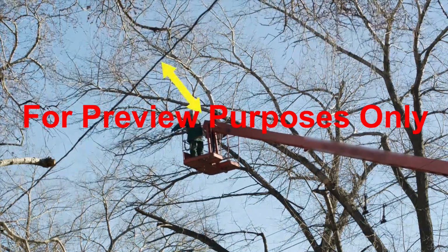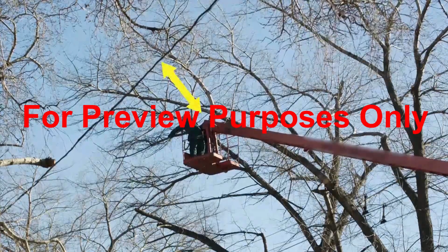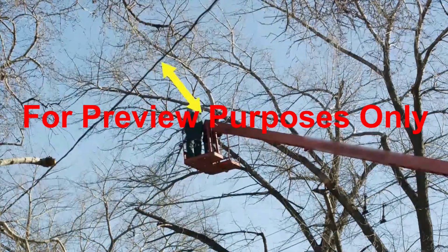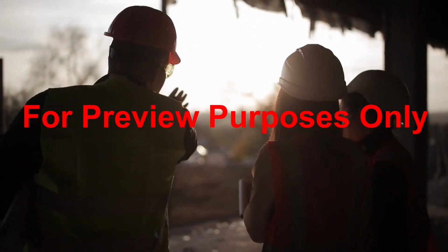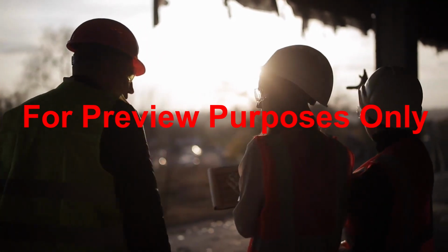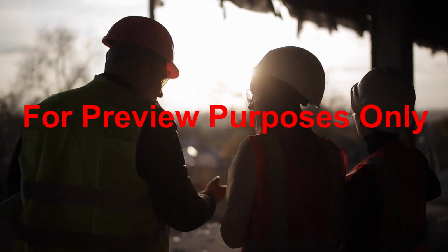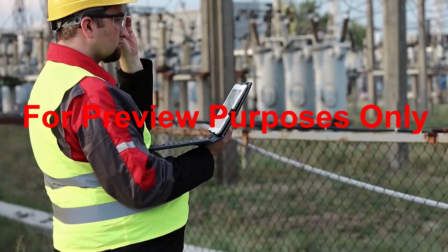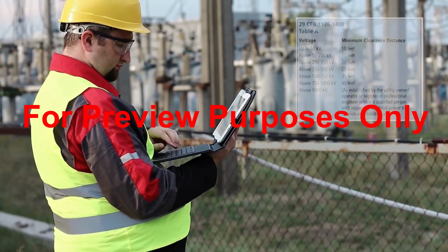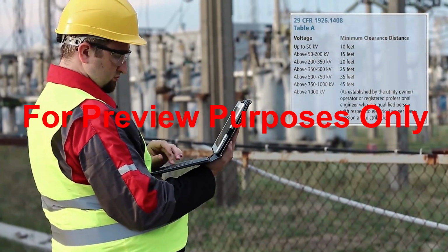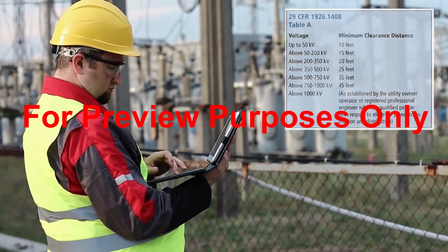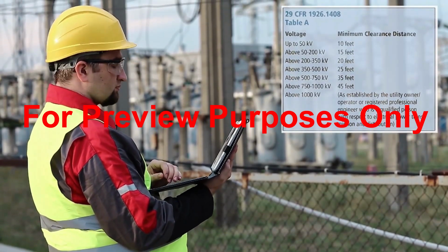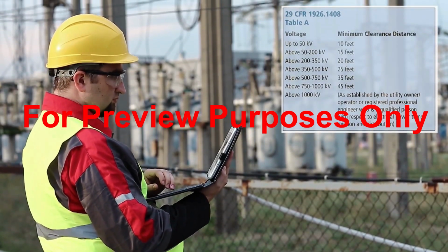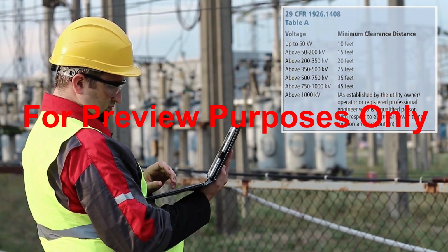That number will tell you how far you need to stay away from the lines to avoid electrocution. If you don't know the voltage in a line, you should assume that it's enough to kill you and stay at least 10 feet away. When you do know the voltage, you can use the table in OSHA's electrical safety standards to determine the safe working distance. This distance increases as the voltage increases.